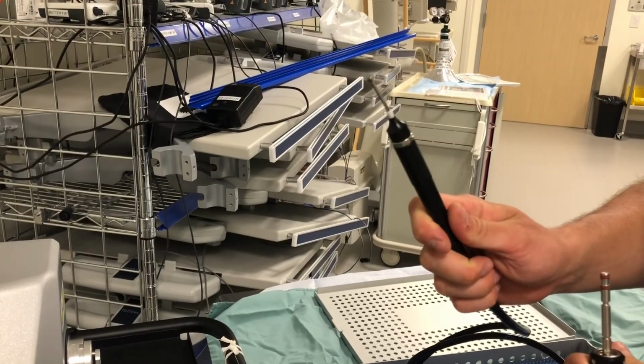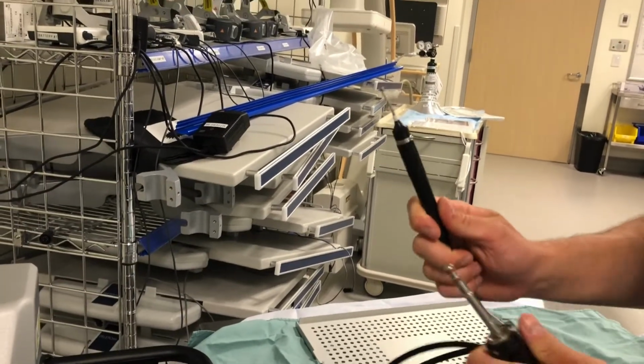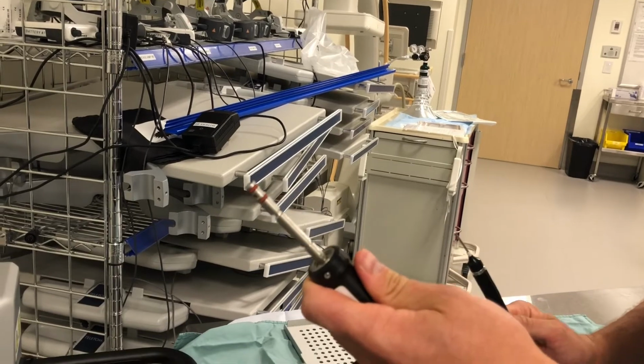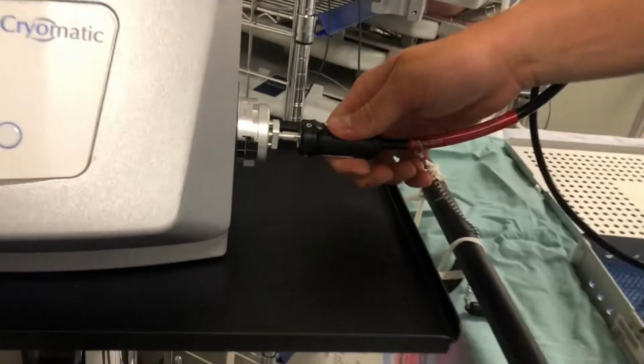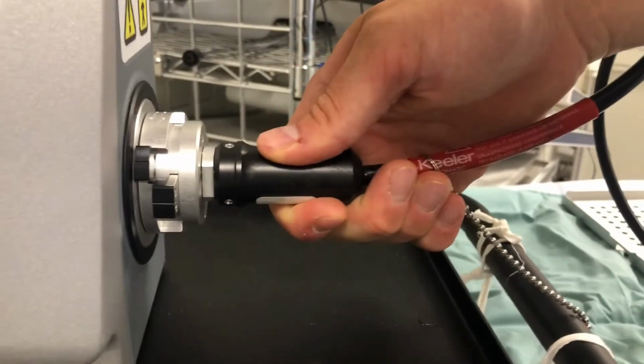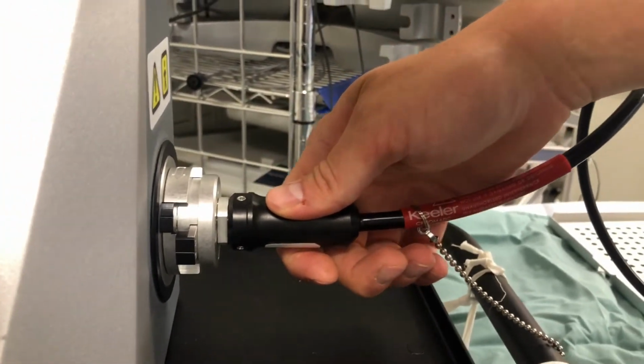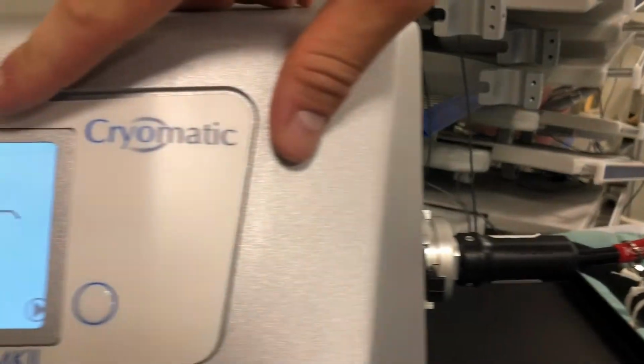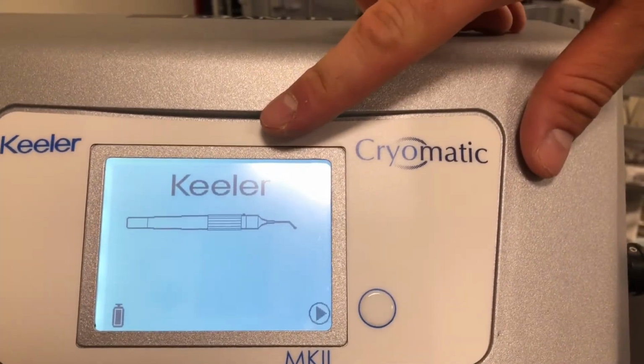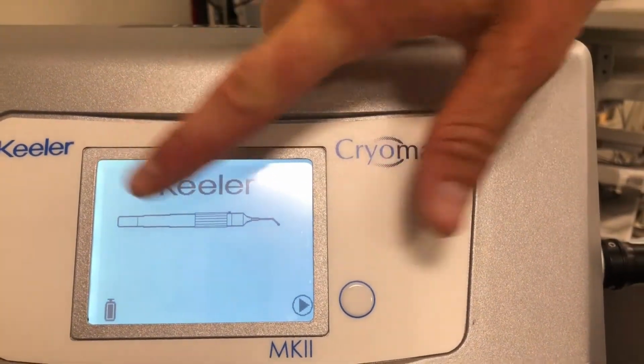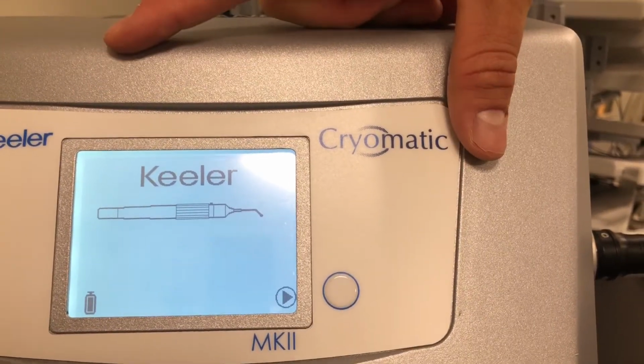So very important never to touch this tip while it's priming. This is the end that goes into the machine, and it's just a full push straight in until you hear a click. When you hear that click, you can look at your digital display, and you'll see that the type of probe you've plugged in is now displayed digitally. That means it's ready to go.